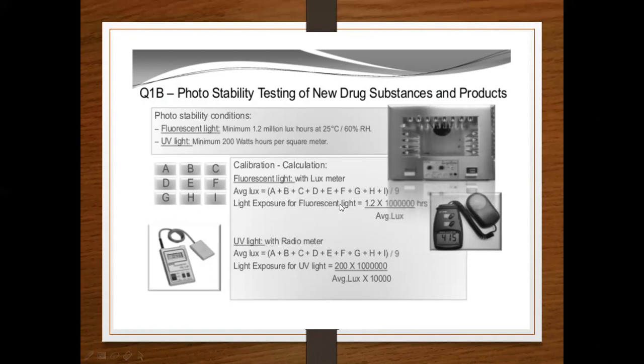For light exposure calculations: fluorescent light exposure = 1.2 million lux-hours divided by the average lux reading. UV light exposure = 200 multiplied by 1,000,000, divided by average lux, multiplied by 10,000. These calculations are performed using a lux meter for visible light and a radiometer for UV light.